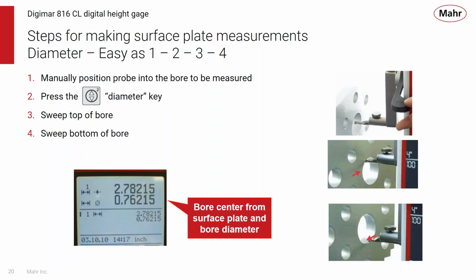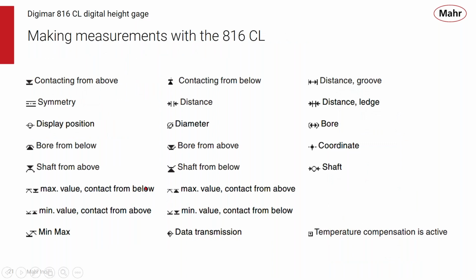The 816 has a pre-built-in measuring routine to do that. And whether you're measuring contacting from above or below, all these features are automated and pre-programmed, and are available for the operator to easily make a measurement. But again, contacting from above and measuring the bore diameter are the ones that are most common and that you're going to use. Whether it be a bore or a shaft diameter, there are functions for that. Just like the min-max function, it's a simple key operation to look for a flatness measurement, for example. All these functions are available either directly or through the function key, and they all guide the operator through making that specific measurement that you want to make.